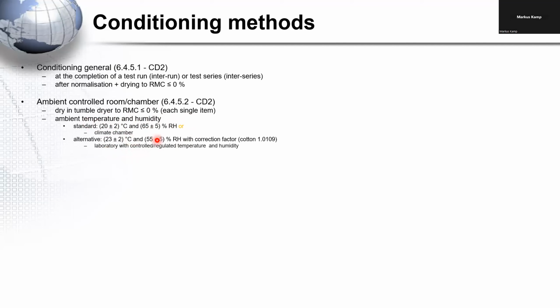This was introduced. There you have the ambient conditions, what we normally have in the laboratory room, 23 degrees and 55% humidity, but these both must be controlled or regulated. That means you have to use a device which is regulating your humidity in the laboratory room, and that is not so common. But if you have such a laboratory room, you can use these alternative conditions, but at the end you have to be aware that you have to apply a correction factor, which is based not on the load, but on the textile type you are using. For cotton, it is this factor, but this is written in the standard.